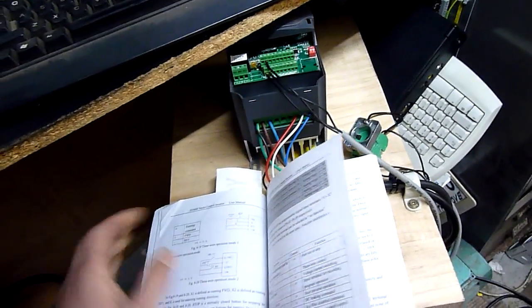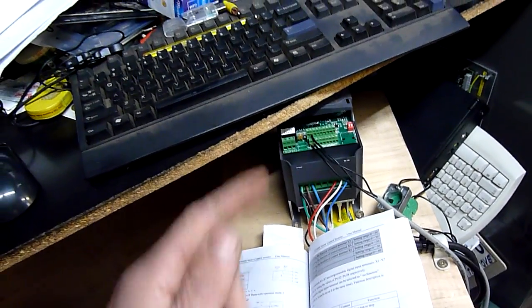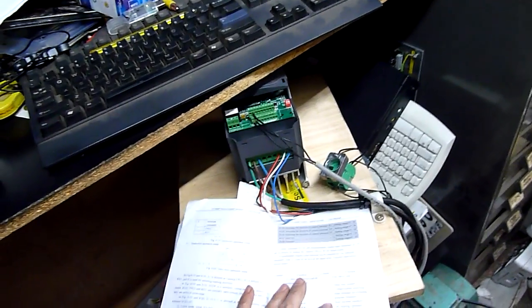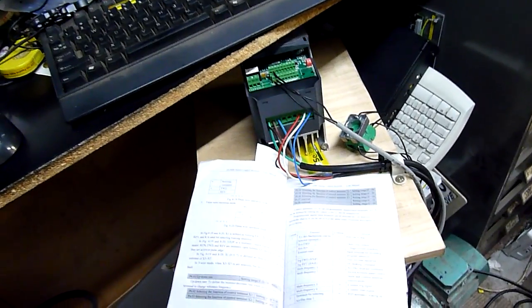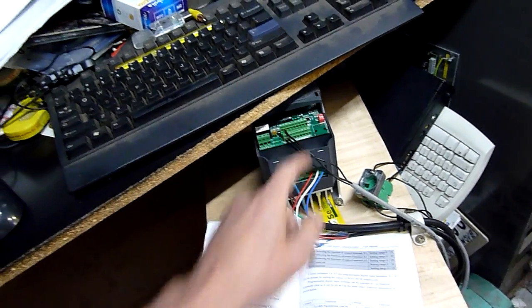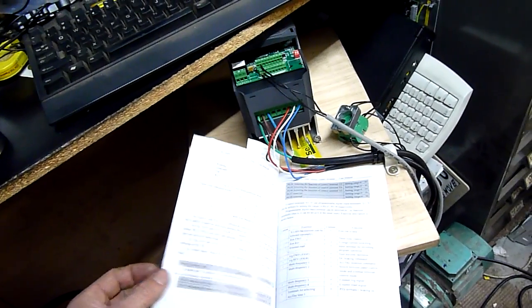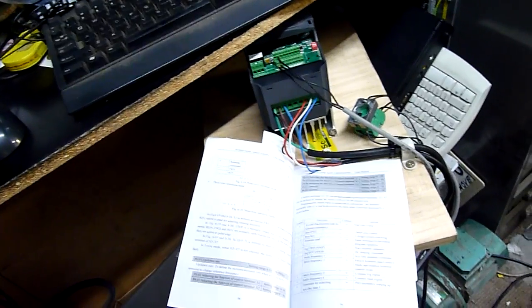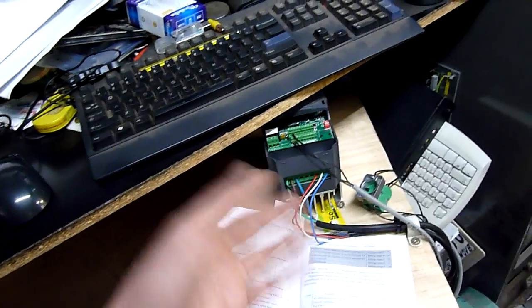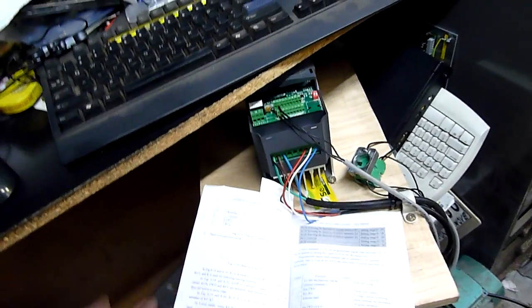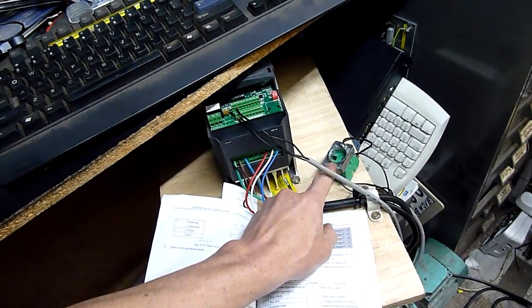But yeah, this light came on, that little one at the top there came on as soon as I enabled the external on. That's technically telling me the keypad's actually doing it, but it's not. So something's ass about in this drive, I don't know if it's just this drive or all of them, but that last command, setting for external control, is reversed. That's all I can figure, that's all I can tell from this thing, because I did everything else by the book, and it didn't work. As soon as I tell it to run off the keypad, which I noticed, I had it set to run off external, but I could still use the keypad, which I sort of expected maybe you could do that, but no. Now I've got it set right, I can only forward reverse with this, the keypad does nothing. I can press start, stop on that, and it does absolutely nothing.